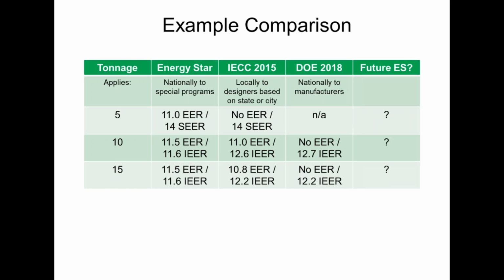10-ton, which is the bread and butter everyday rooftop unit everybody uses in their examples: 11.5 EER, 11.6 IEER. But if I look at the local code, the current local code here has a higher IEER and a lower EER. So just putting a code-compliant unit in might not be enough to get me an Energy Star label today.